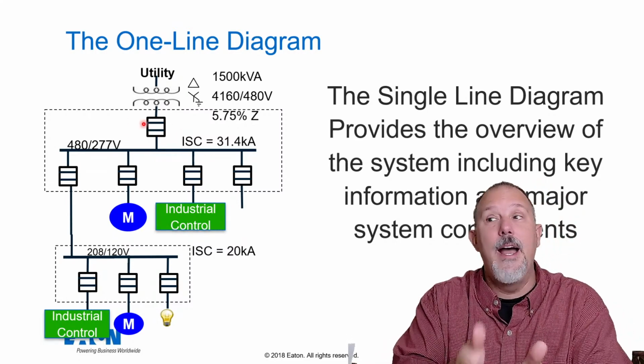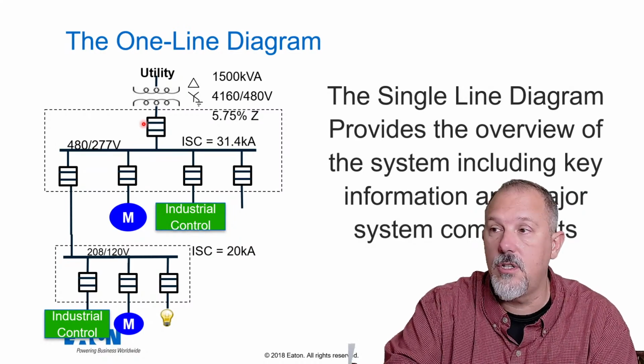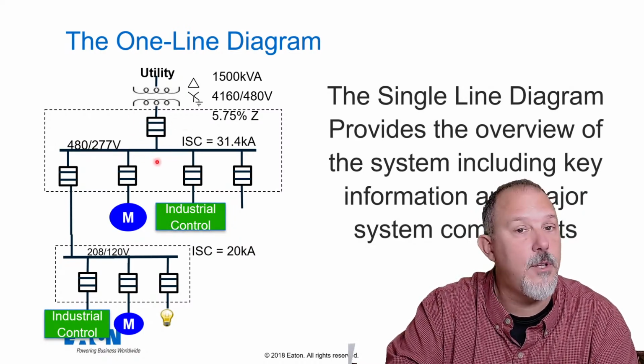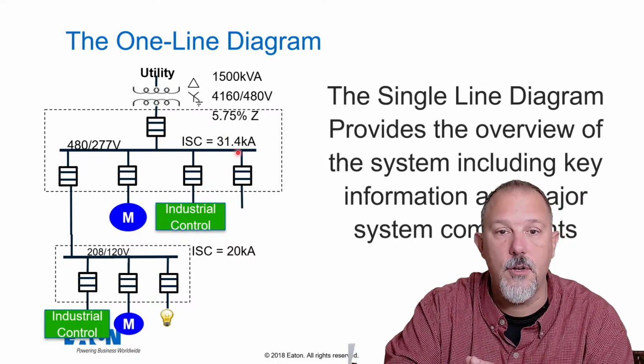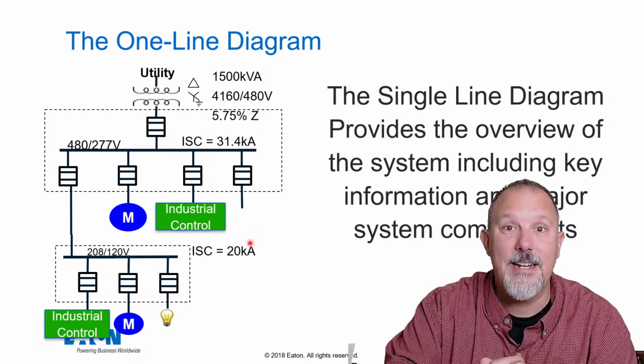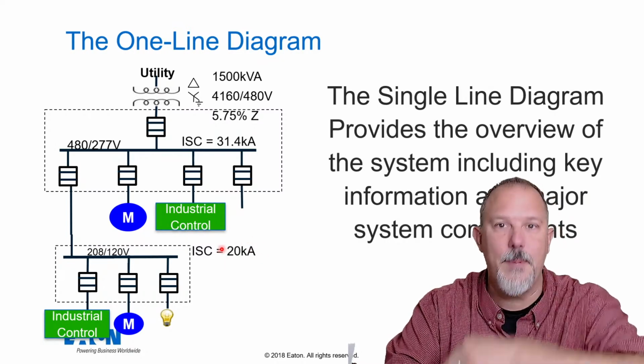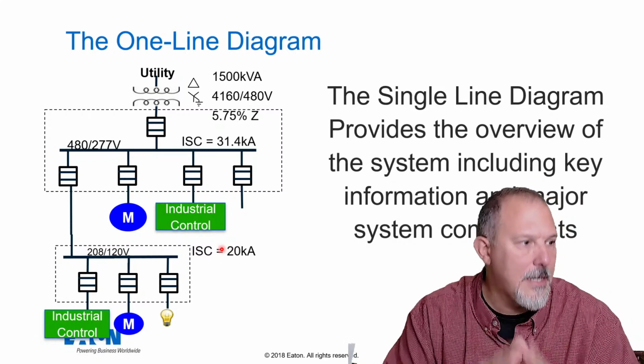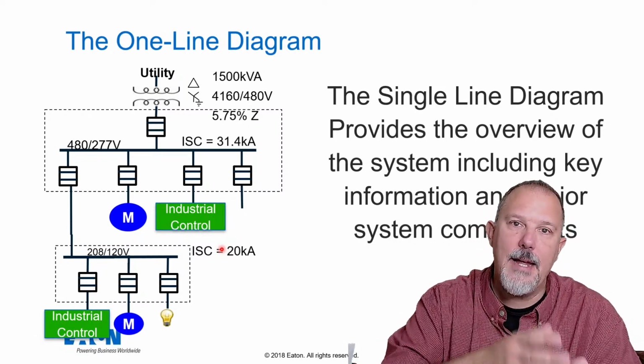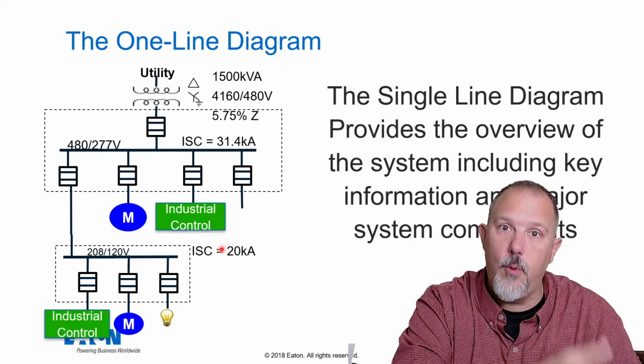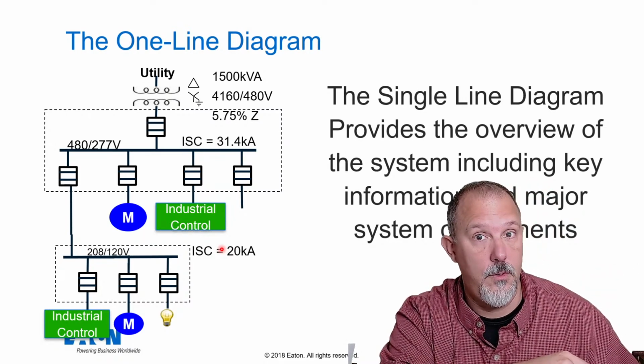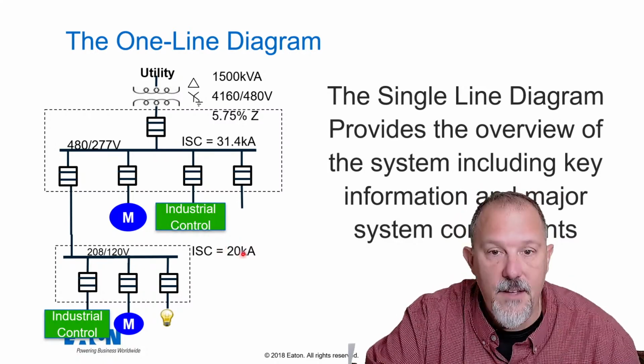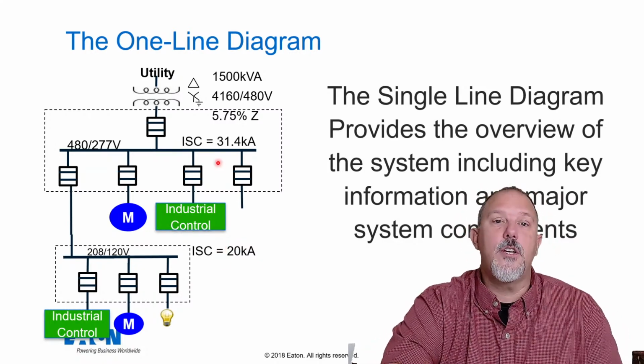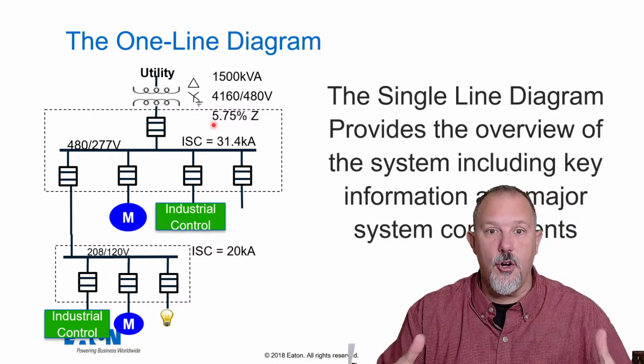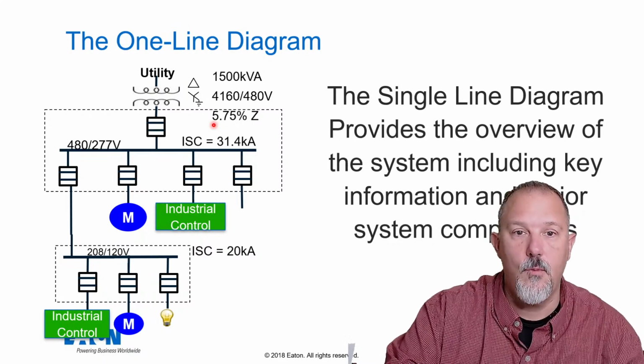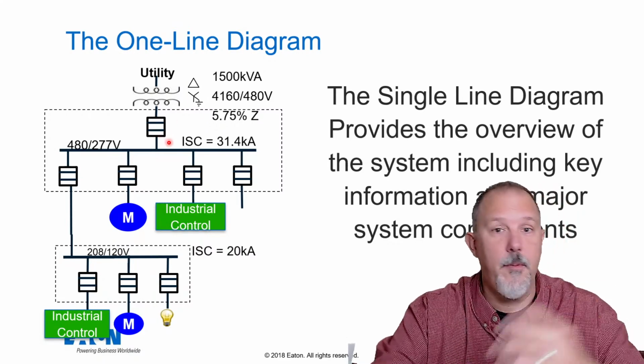And I've had people say, I reduce the fault current in my power distribution system because I have this main fuse. But this fuse is going to react to the fault current of 31,400. It'll react differently for a fault current of 20,000 amps, which will be downstream. I hope that's clear. So I apply an overcurrent protective device to protect the equipment immediately adjacent to it, if that makes sense. Now, if this current of 20,000 amps is in the current limiting region, could one make an argument that it's high enough that this device will go into current limitation? You could probably make that argument.